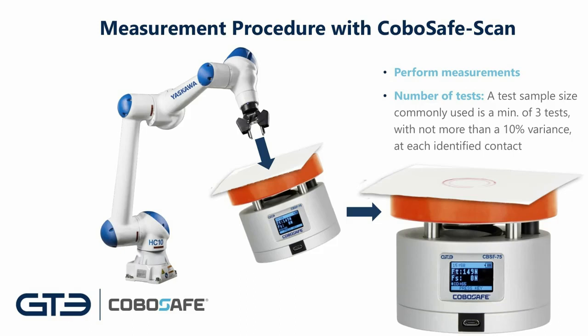Number of tests. For example, if your goal is only safety, and your measurement results are, for example, 50% below your threshold, then you will not exceed your threshold in subsequent measurements. If you want to optimize your application, so that means getting as close as possible to the threshold, the test sample size most commonly used is a minimum of 3 tests with not more than a 10% variance at each identified contact.